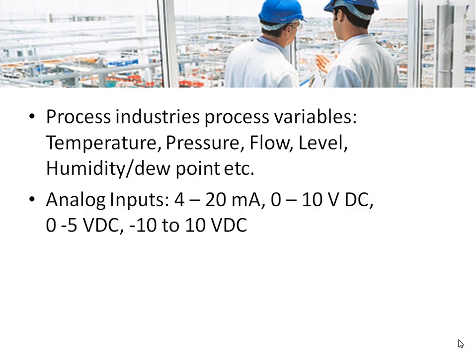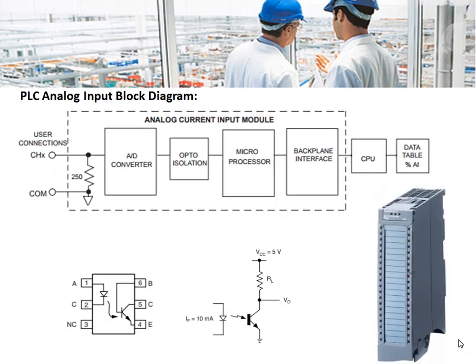At the control room, before feeding this analog signal to the CPU of the PLC, it should be converted to a digital signal. The block diagram of a typical analog current input module is shown in the figure. The current coming from the transmitter is converted to a voltage by using a 250 ohm resistor.